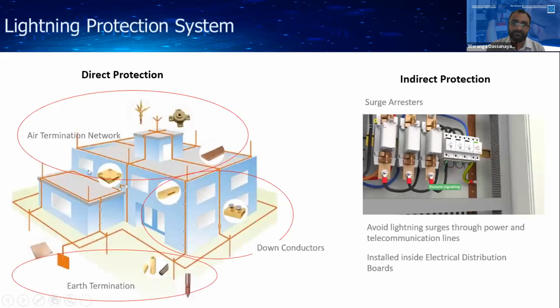This is the pictorial view of a lightning protection system. The top part we call the air termination. Then the second part we call the down conductor, and the earthing part we call the earth termination. And for indirect protection, these are called the surge arresters.